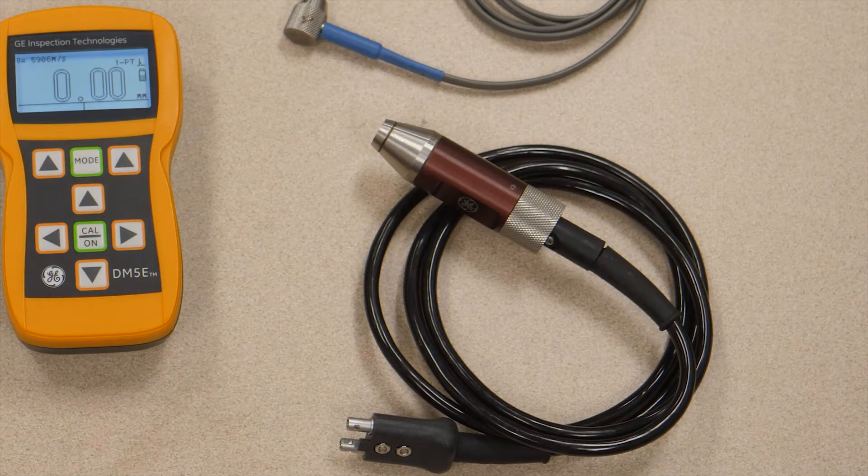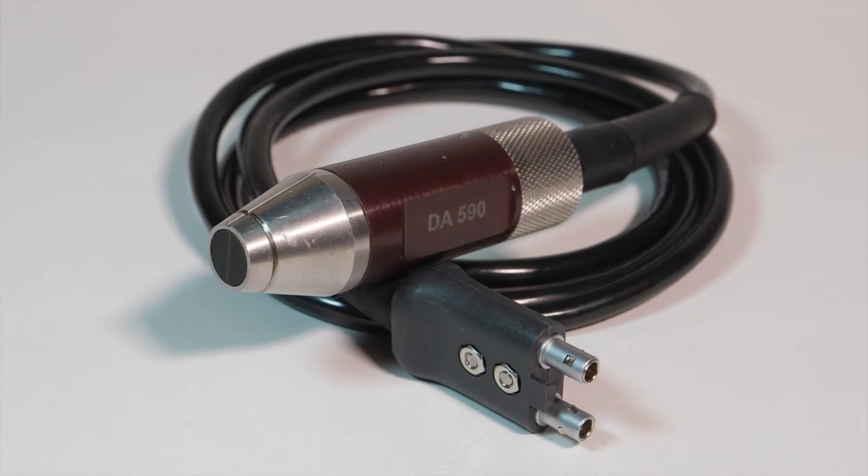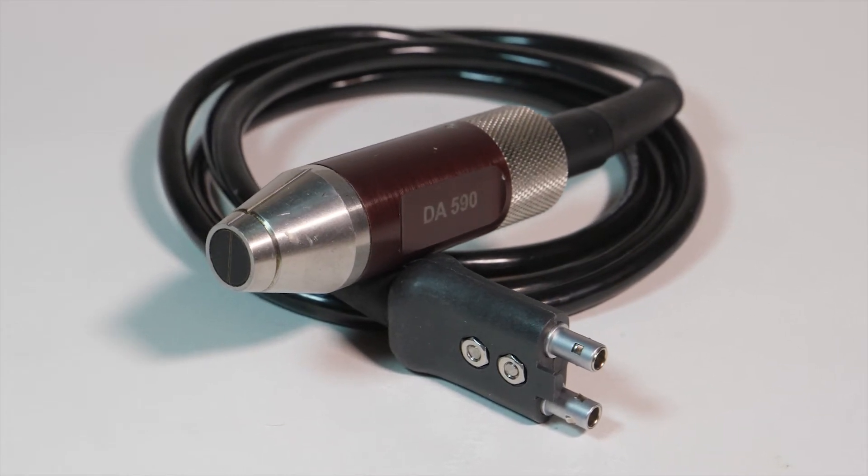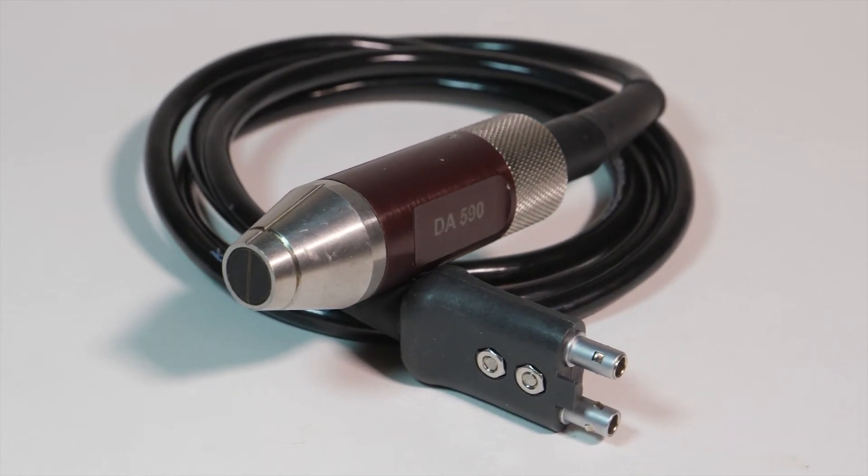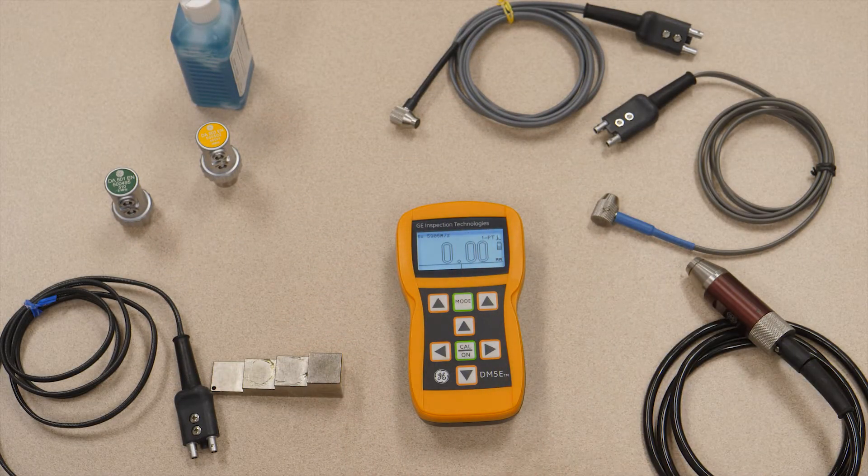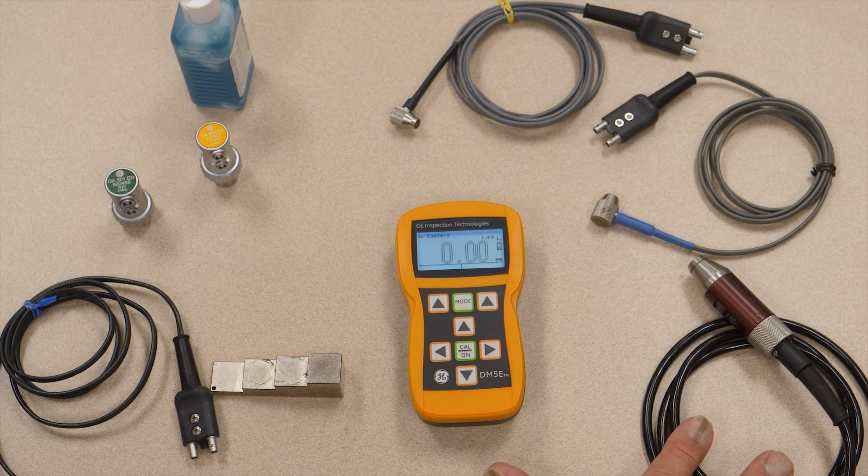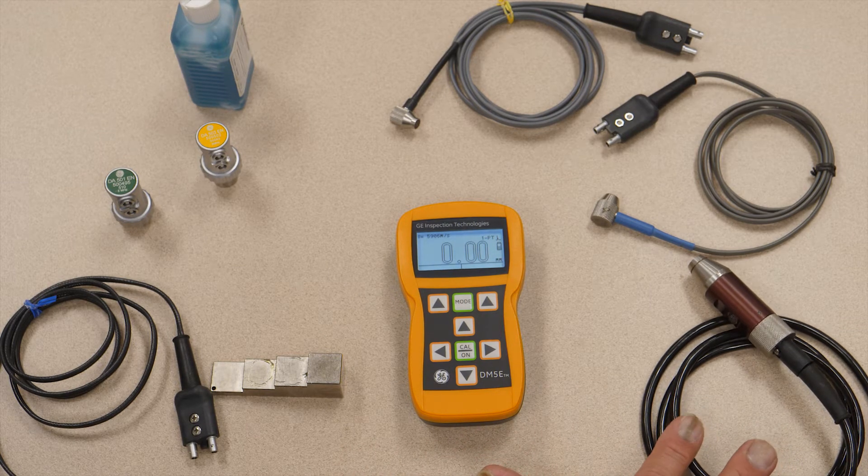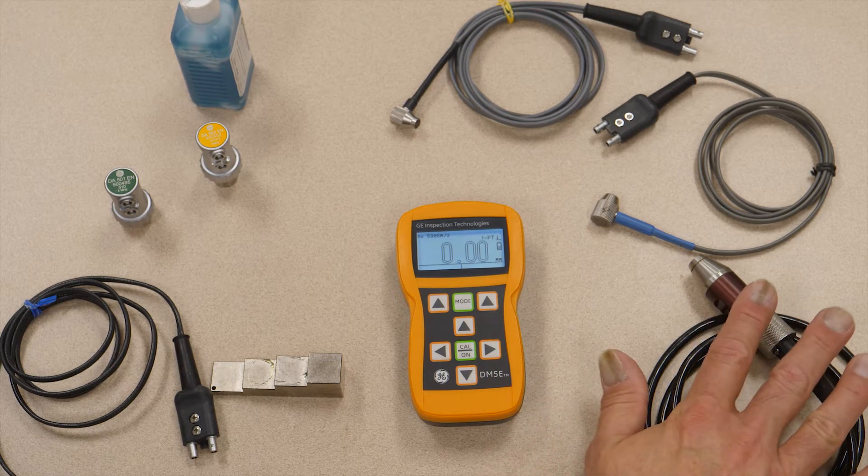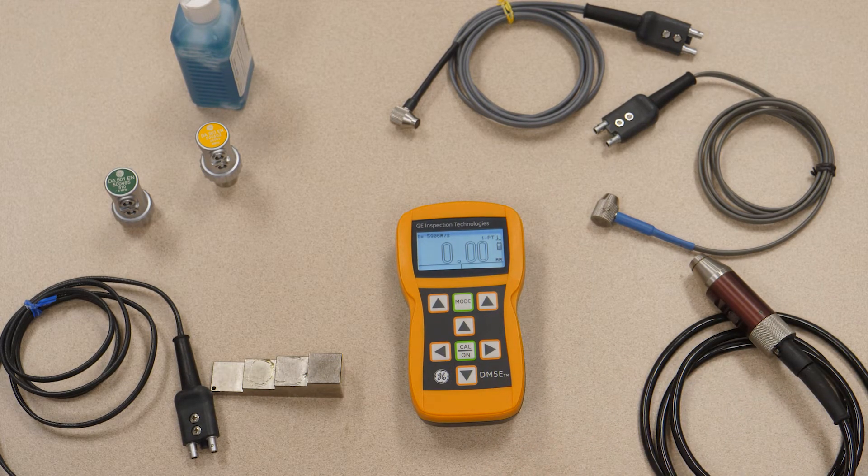And we also offer the DA590, which is a high temperature probe. You can measure on materials up to four hundred degrees Fahrenheit with this probe. Now the DM5E, unlike the DMS-GO our more advanced gauge, doesn't offer temperature compensation for the measurement. So you're still getting the raw thickness measurement, but the DA590 probe is available to work at higher temperatures.